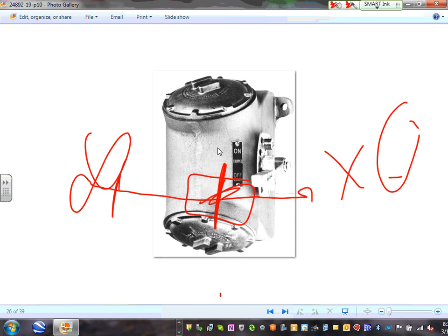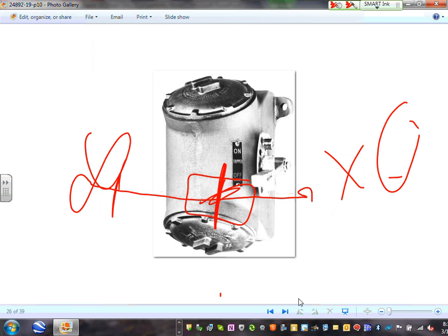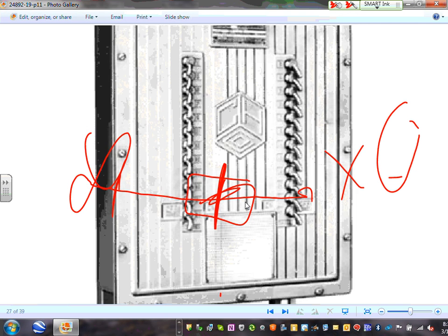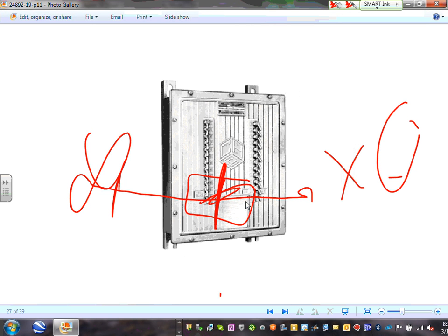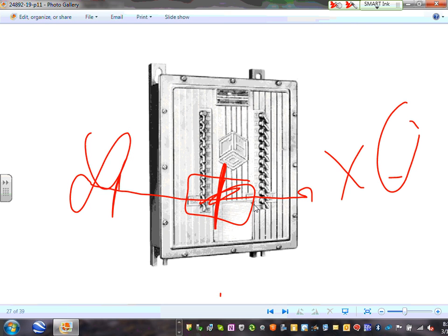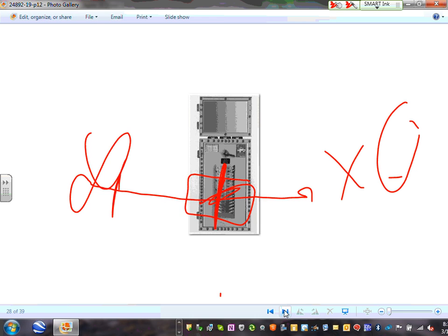Look at how big. This is a circuit breaker. Can you guys see? That's an explosion-proof circuit breaker. You're looking at 10 times, 20 times more expensive. That's a big boy circuit breaker. So look at the panel. The panel, lots of bolts. So if there's an explosion, it holds that explosion. Very expensive, very bulky equipment.